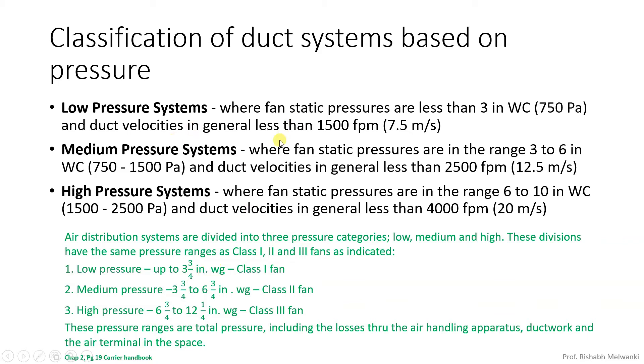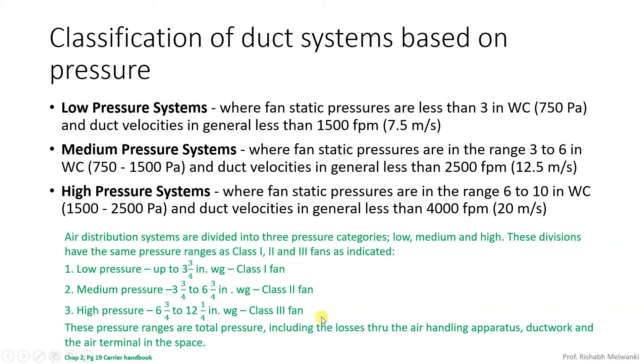One deviation is that the earlier classification used 3 inches of water column for static pressure, while the carrier handbook uses three and three quarter inches for total pressure in the low pressure system. This is because one classification is based on static pressure and the other on total pressure. Then we have fresh air duct classification.